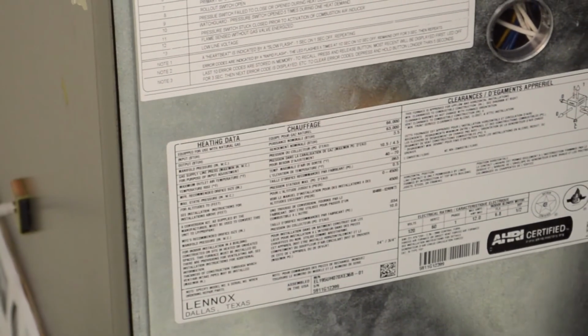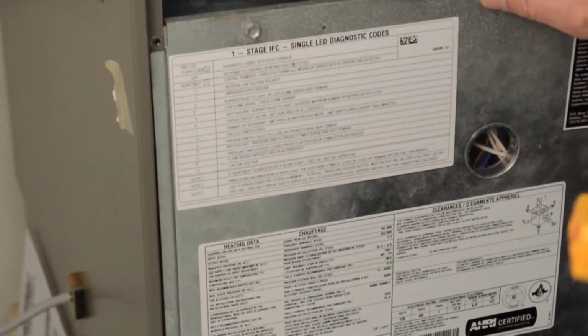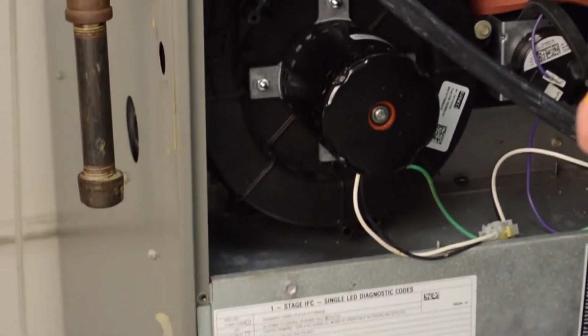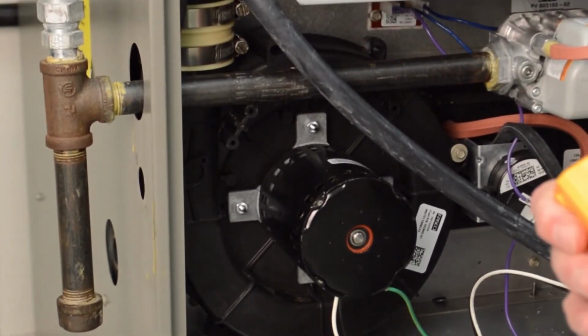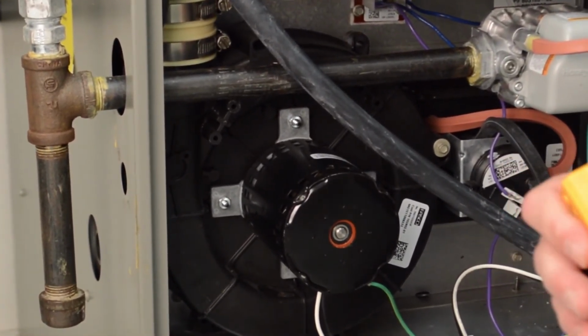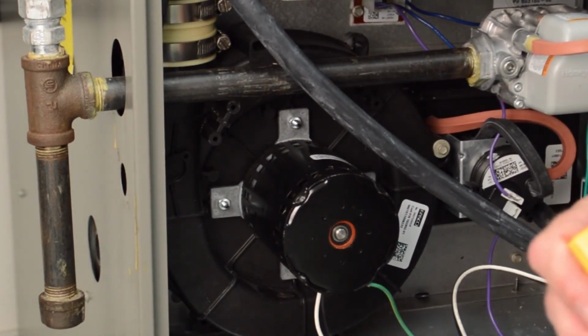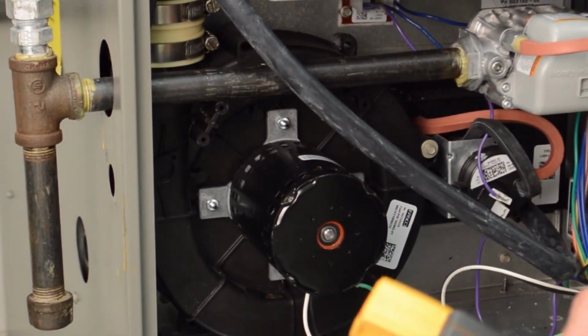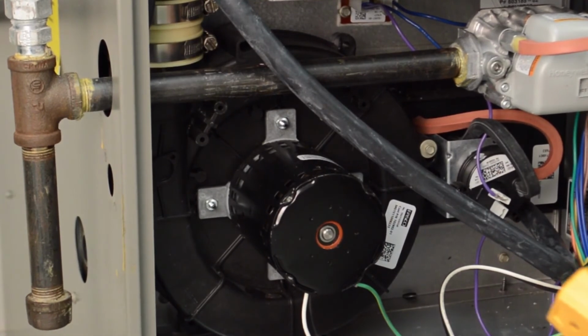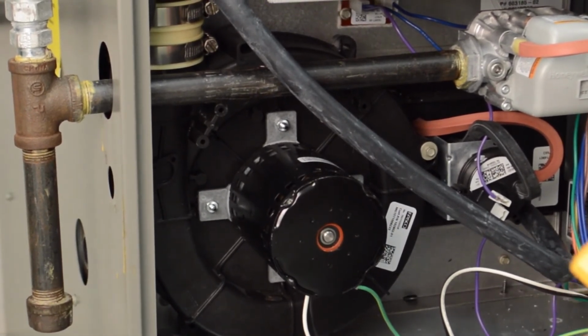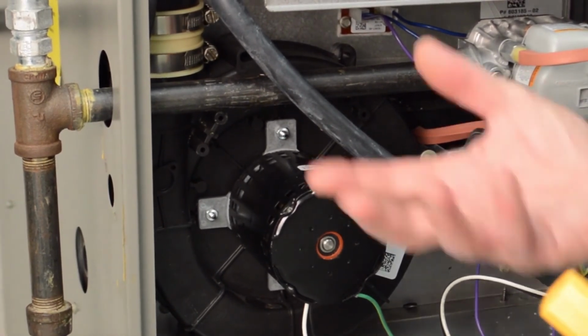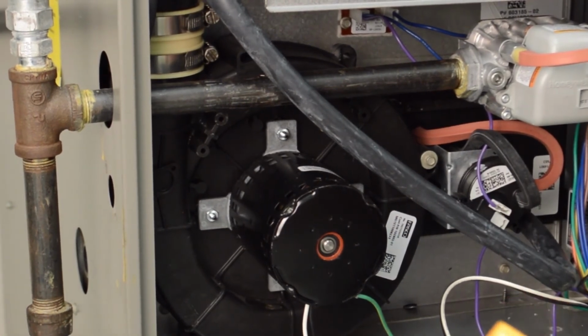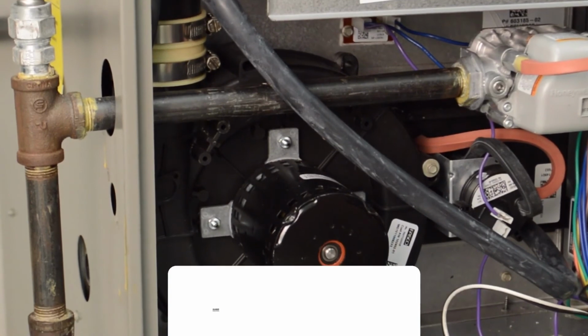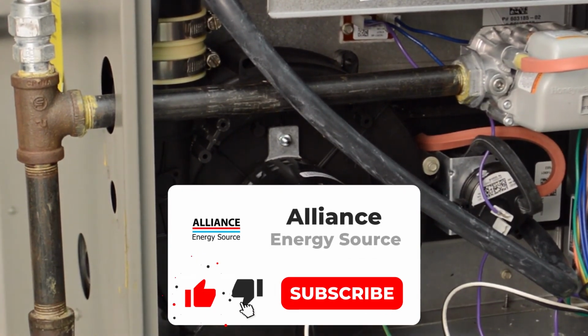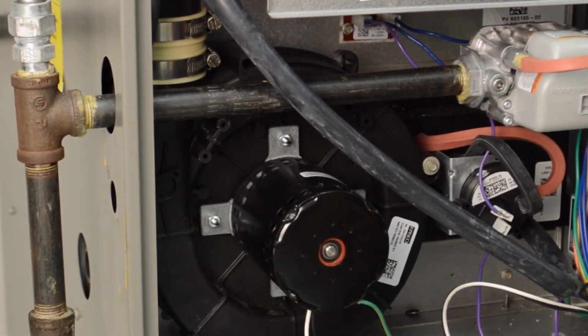If that number is too high, we need to figure out why. The most common reason of that being too high is that the blower motor is set too low, or the filters are plugged. So we want to double check the filters, make sure that those are clean or out in this testing phase. If that is fine, then we look at other problems, either restriction of the ductwork or we increase the air by changing the blower speed. We'll cover that in a different video. If it is not high enough, we're going to slow that blower speed down to allow the air to pick up more heat.